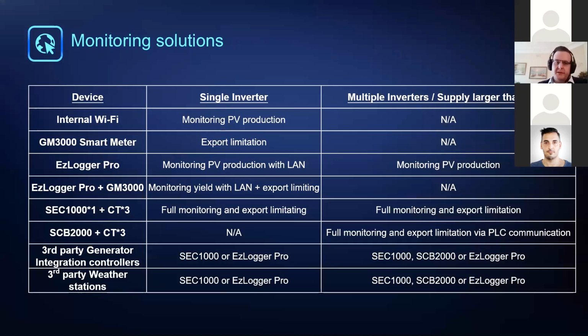With our multiple inverter setup, if your supply is larger than 120 amps, you'll need to use the SEC1000, because the CTs that are included with the GM3000 are only 120 amps, and they are not exchangeable. If you just require PV monitoring of a multiple inverter plant with no limitation, you can just install an EZ-Logger Pro. If you want the full monitoring with the load monitoring and export limitation, the SEC1000 is the way to go.